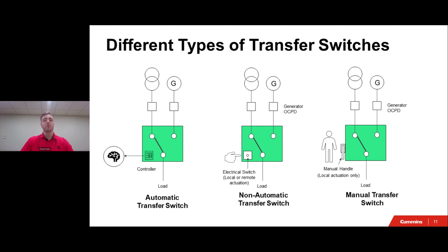Please keep in mind that for this type of switch, the switching mechanism used to switch from one source to the other is still operated electrically. So as you can see, there's that little hand there pushing the button, the electrical switch. So the difference between that and automatic is that the switch is either done locally or through a remote actuation.